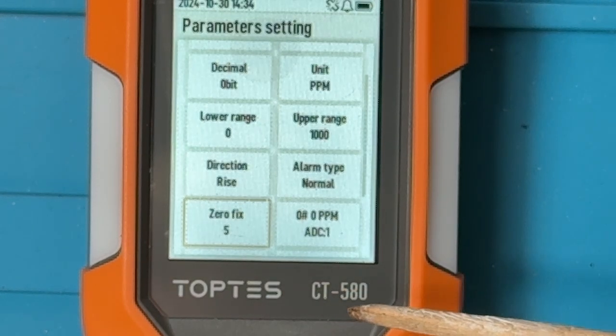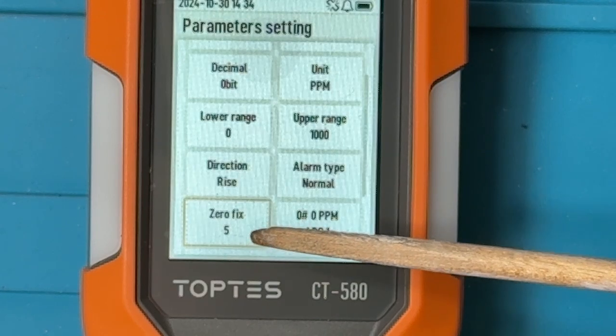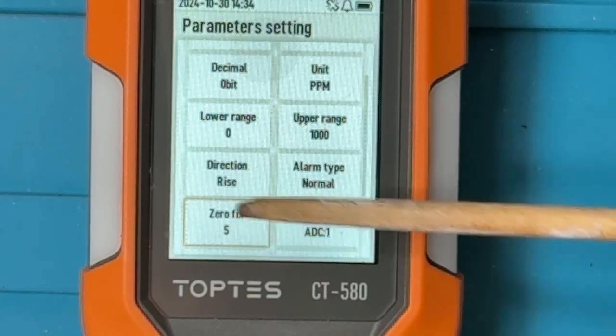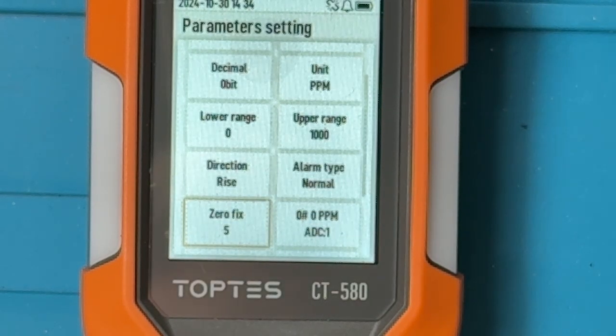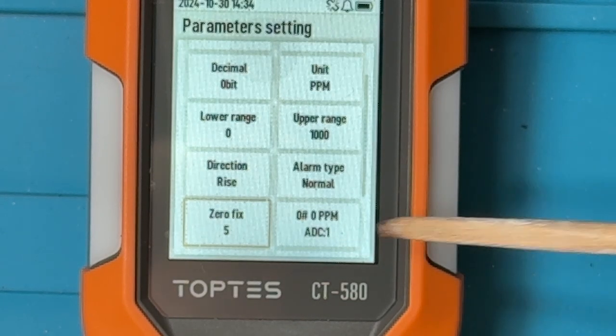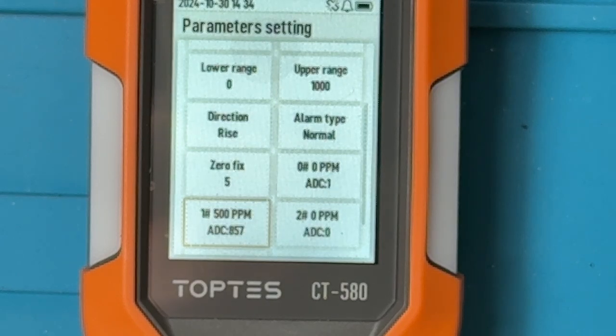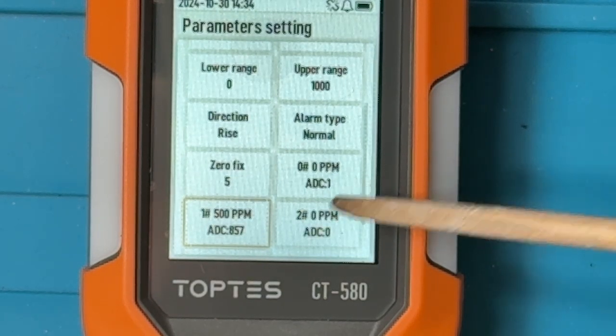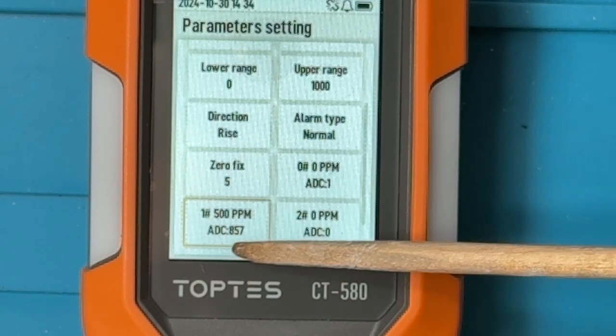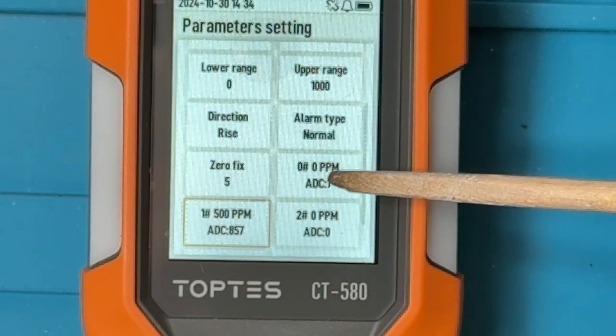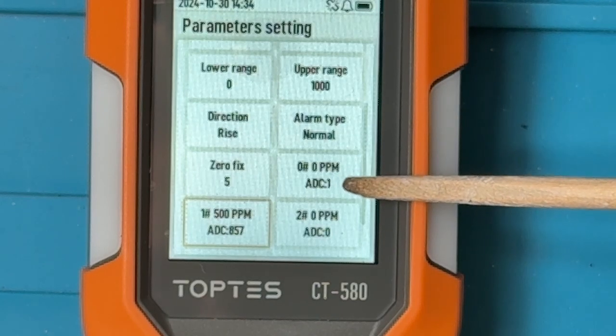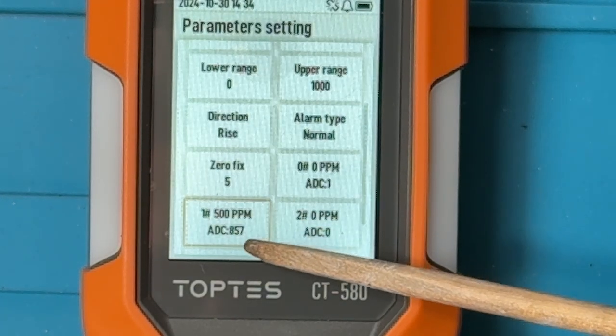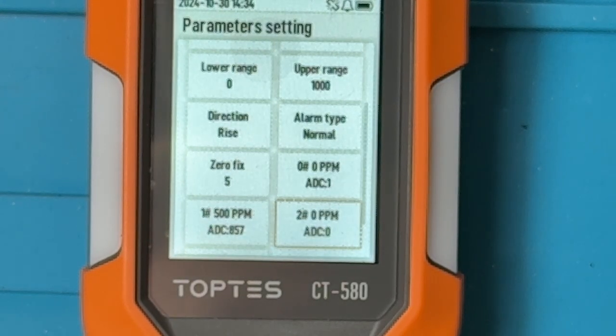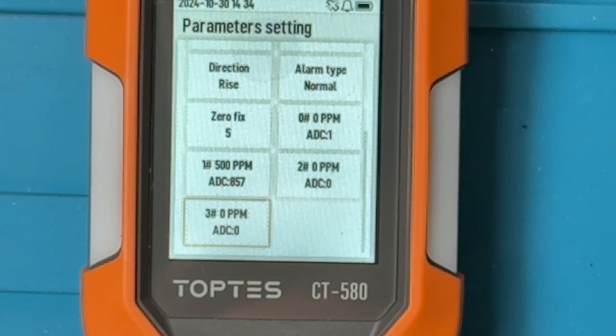We have a zero fix. And that eliminates displayed values near the 0 point, in order to eliminate noise at very small levels. And then a little bit of information about the analog to digital converter. It's basically telling us what values coming out of the analog to digital converter are used to indicate different concentrations. So 0 parts per million is an analog to digital converter value of 1. 500 parts per million is an analog to digital converter value of 857. Okay, and the 2 and 3 values don't appear to be used in this unit. So that's what's available to us in terms of the sensor settings.